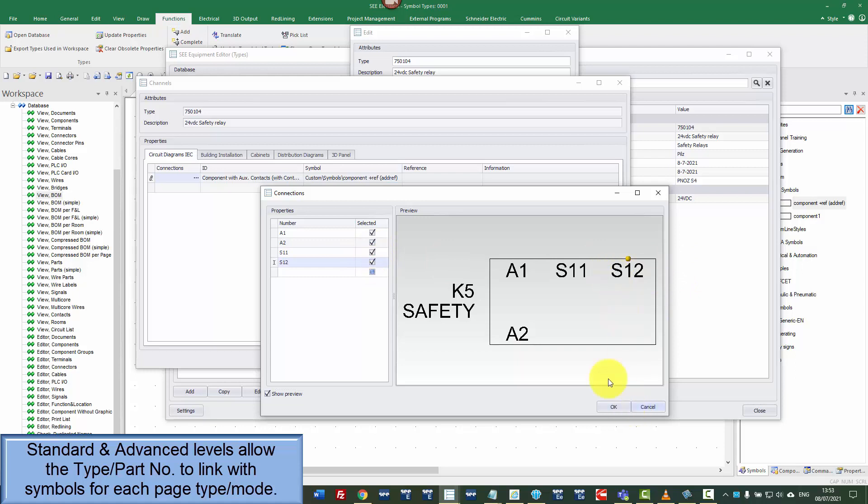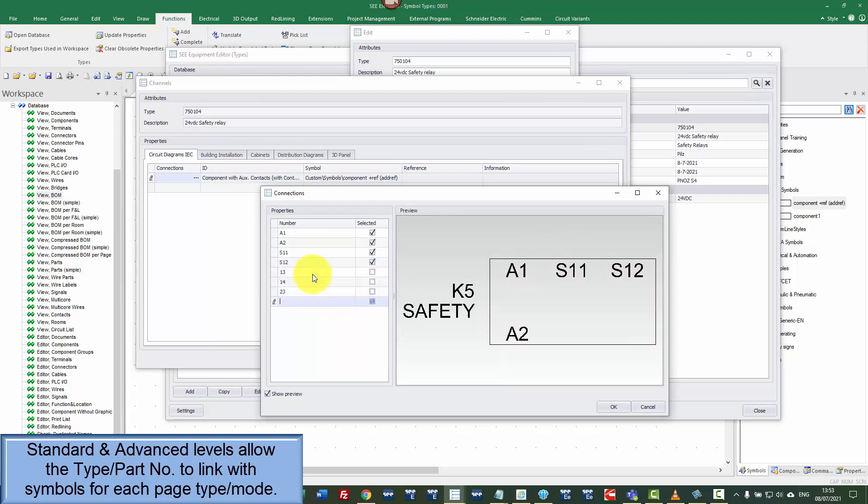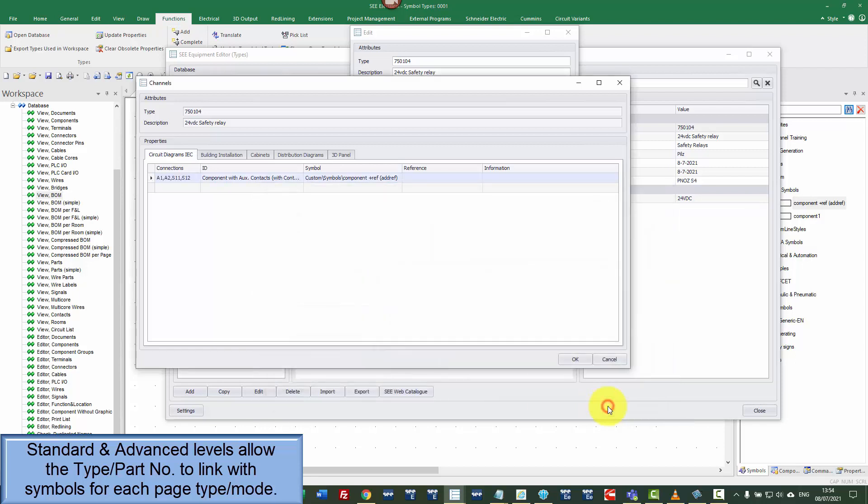Now, on this symbol, we could just choose the main component but it's also got some additional contacts so I'm going to put in here 13 and 14, 23 and 24, 33 and 34. And it's also got a closed contact so I'm going to put in here 41 and 42. So I've added the extra connection points but they don't get assigned to the main symbol.